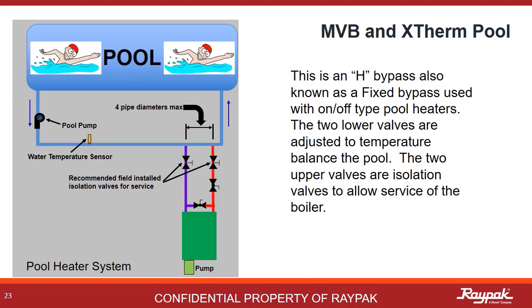As with the water heater type, if it is a pool heater, there is only one mode of operation. Here the decoupler is the distance between the supply and return off of the recirculation loop. The two upper valves are there to isolate the heater for service, while the two lower valves are there for temperature regulation.